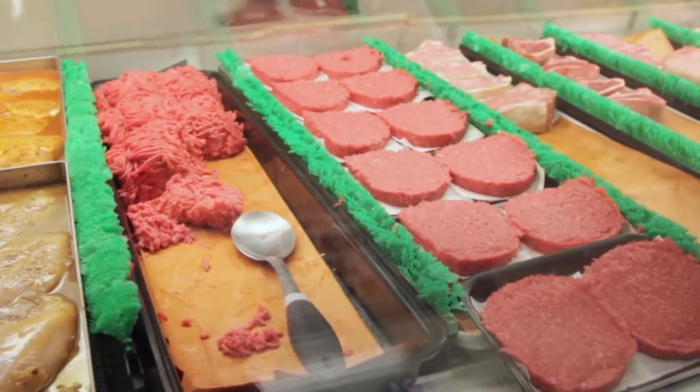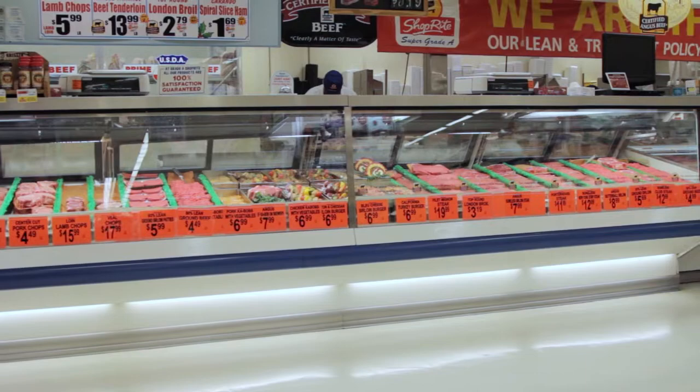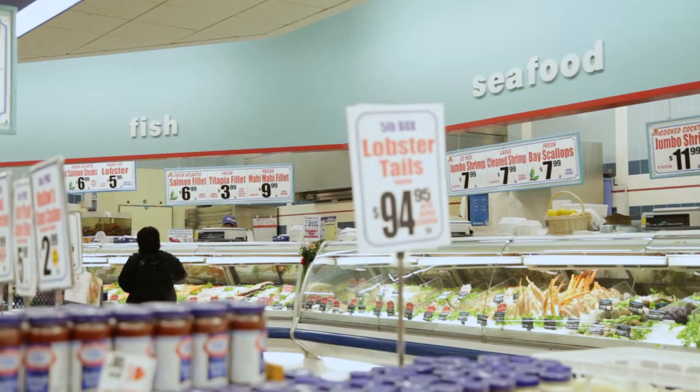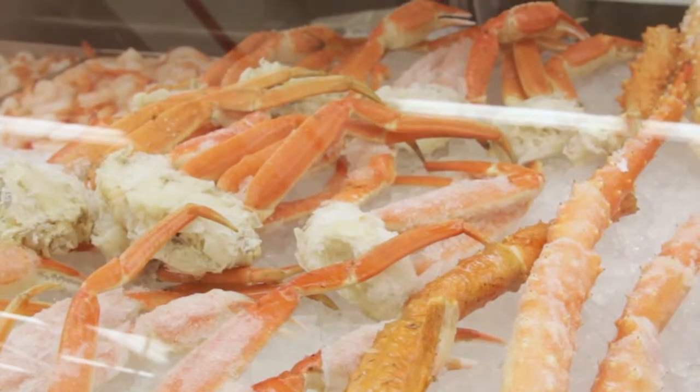While there are varying levels, dehydration continues in all cases, and there's a lot of money left on the table if your service case is not humidified. Any case out there — glycol, forced air, or gravity — I haven't come across one yet where they say humidity is not needed. Glycol cases, for example, when they were first introduced, there was talk about no need for additional systems because they would maintain the product. However, we had a customer in California who, within months of ordering those cases, realized they still needed humidity — they were losing weight and appearance inside their glycol cases.